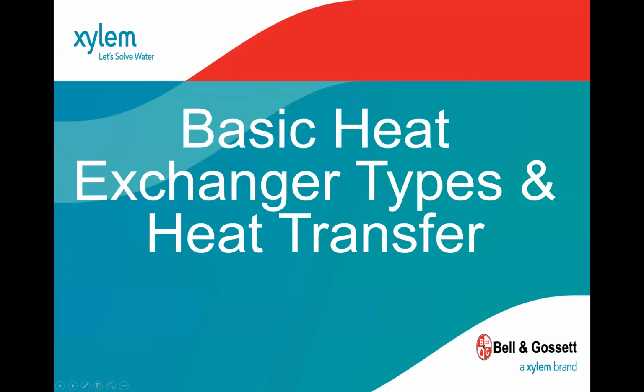So like what we had on this backside, this was showing that if you hold all heat transfer, we also have to factor in co-current versus counter current. Ultimately, counter current gets the best heat transfer. Co-current is about a 25% reduction. Sometimes you'll hear people say that the heat exchanger was piped incorrectly. As long as you have that counter current, whether you put the hot on what was supposed to be the cold side or the cold side on what was supposed to be the hot, it's fine. That comes up sometimes.